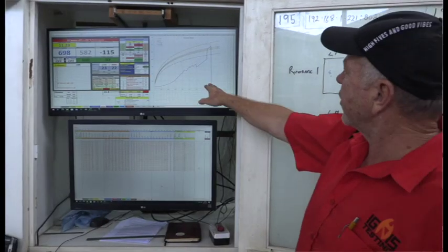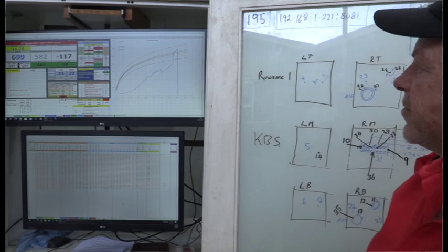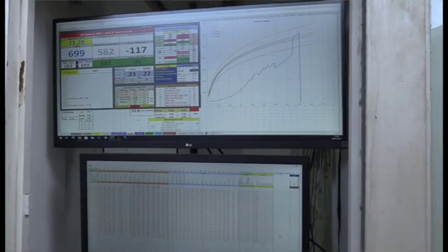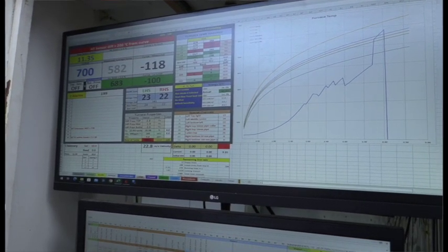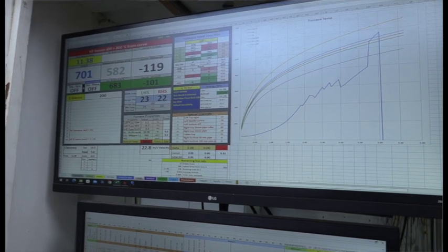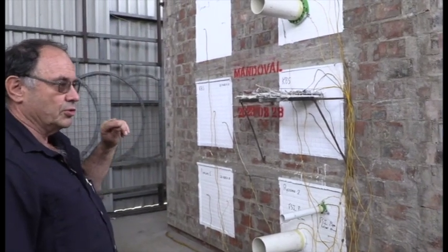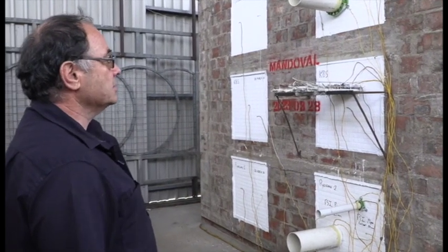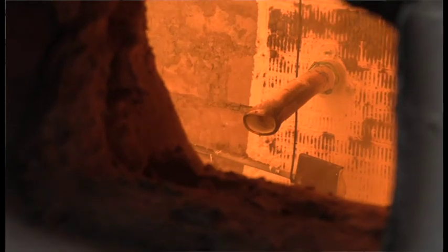The temperature time curve that we follow, they call the standard temperature time curve. It's a curve as old as 100 years already being used in the industry. So it's a reference time temperature curve that is part of the fire industry for 100 years, and we follow that curve as close as we can within the tolerances set by the different standards. Our furnace is set up more according to the European standard, where we actually use 10 plate thermocouples inside. If a thermocouple goes astray, the software will take it out, and we use the average of the remaining ones.